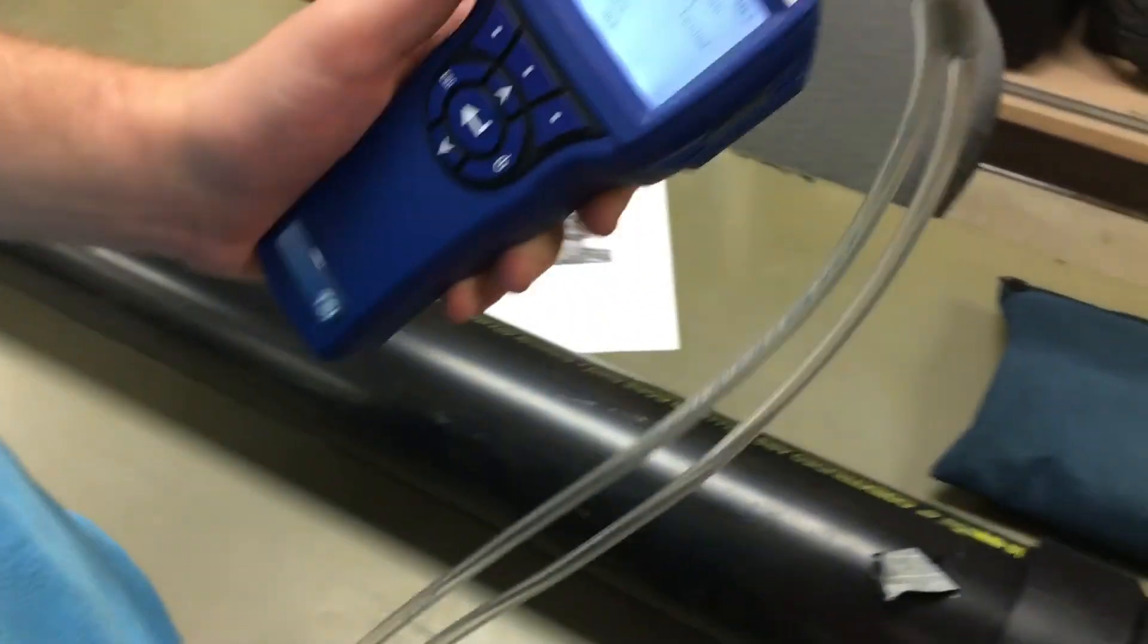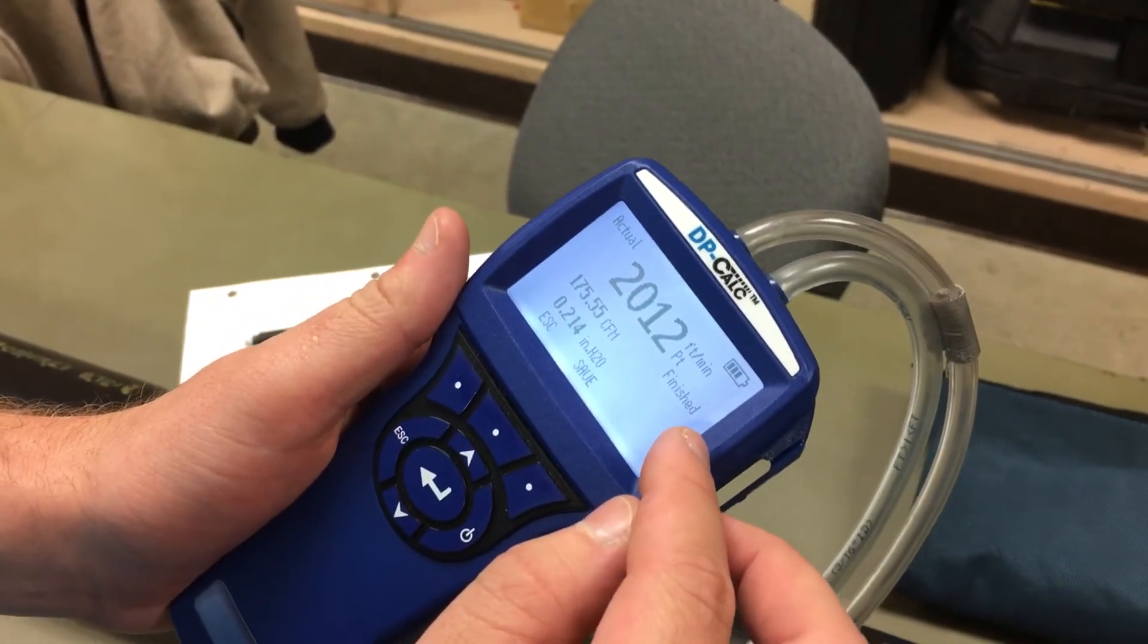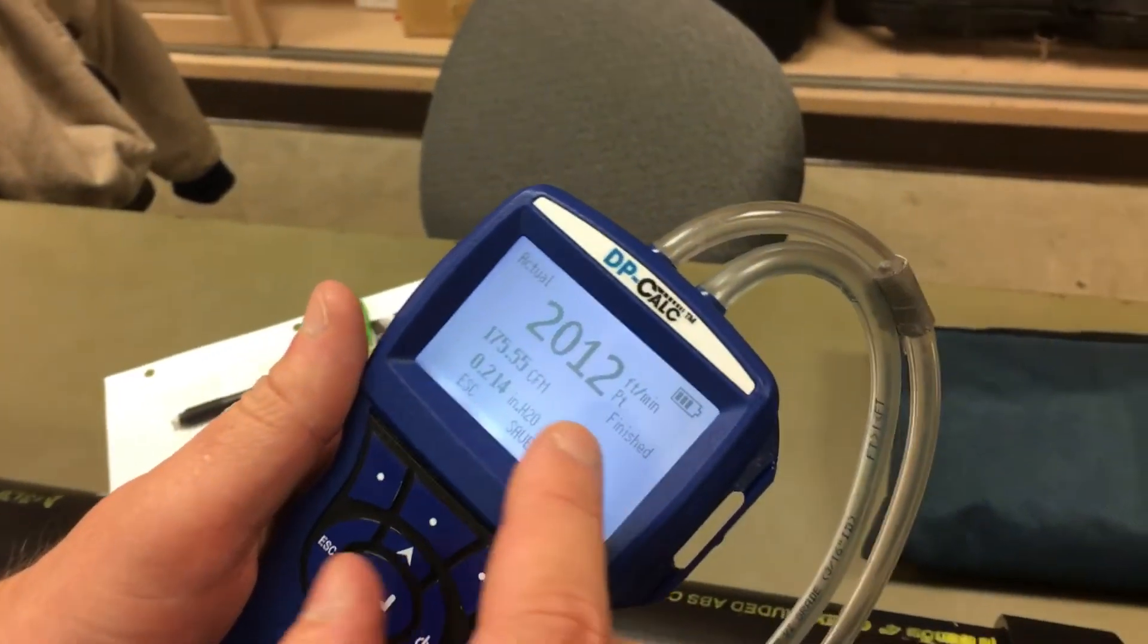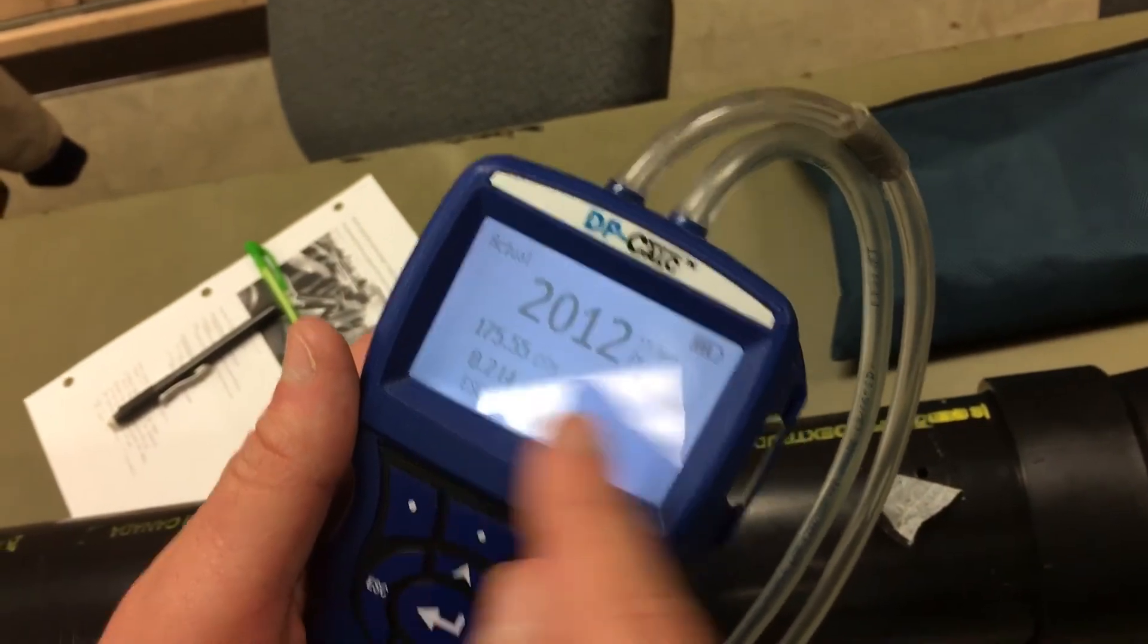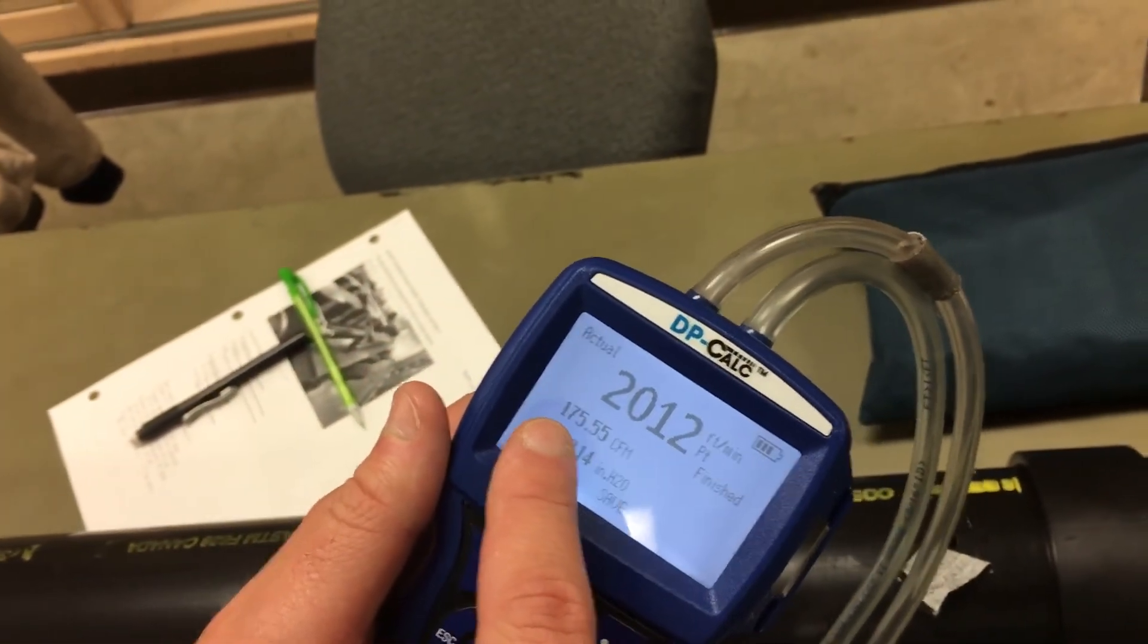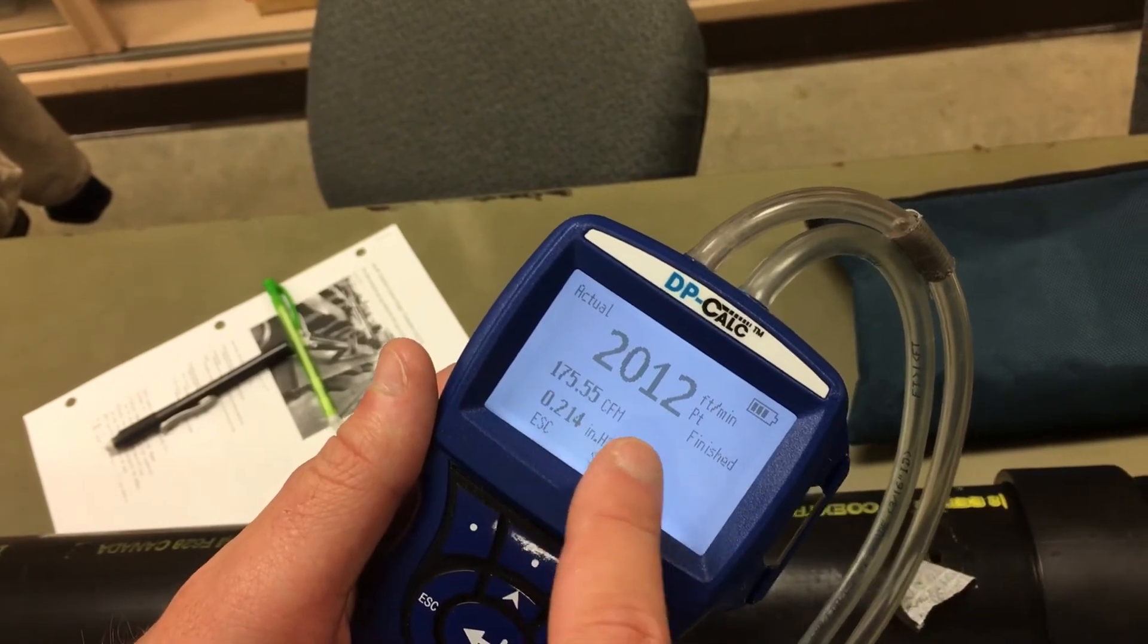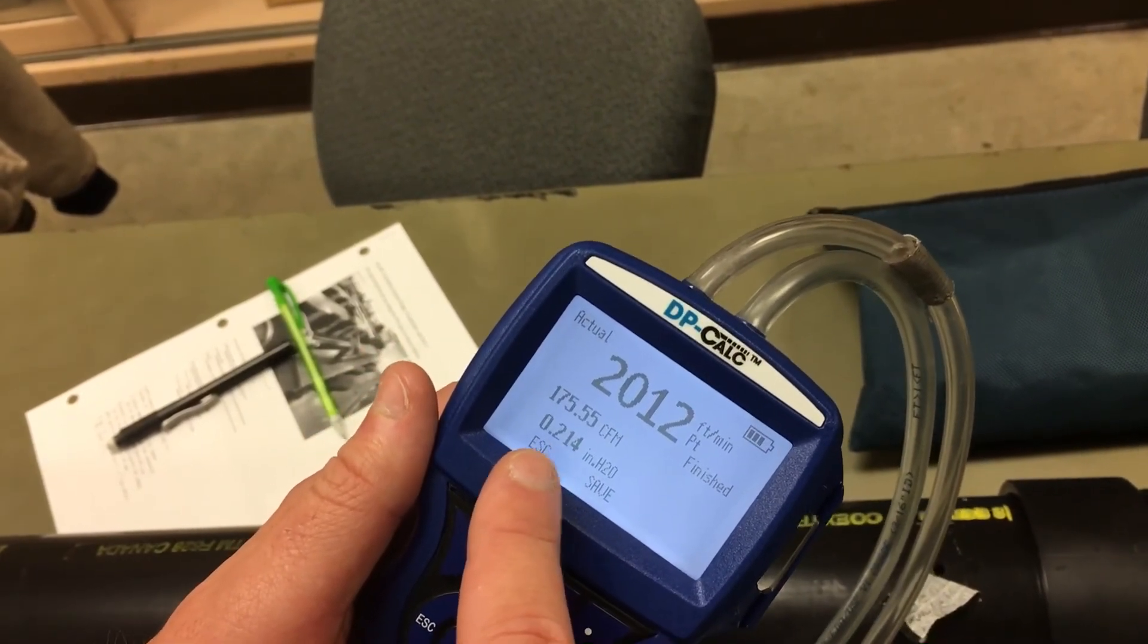I hit the enter button, which measures over the course of a few seconds and gives you an average. For our average, we got 2,012 feet per minute, which with the size of our duct gives us a volumetric flow of 175.55 cubic feet per minute, and the velocity pressure associated with that was 0.214 inches water.